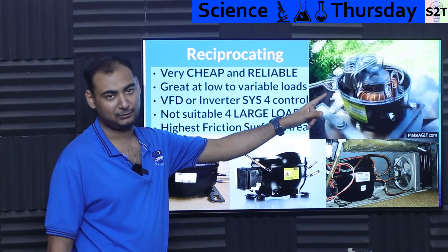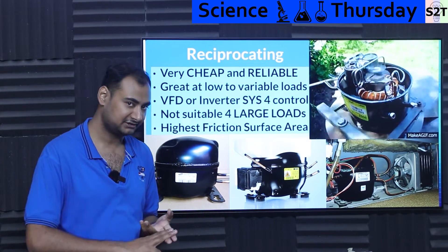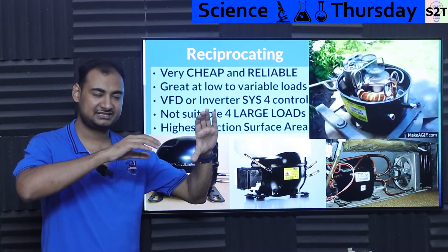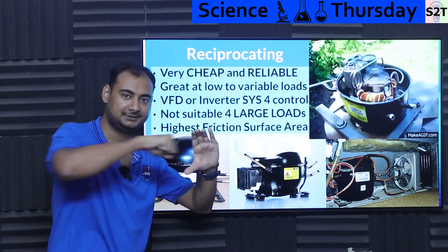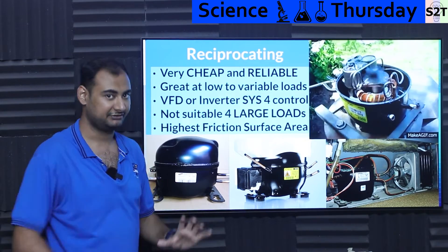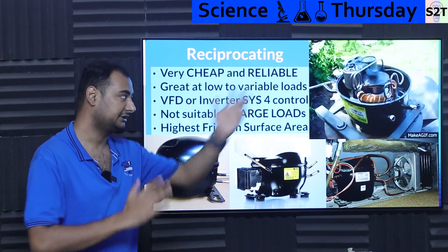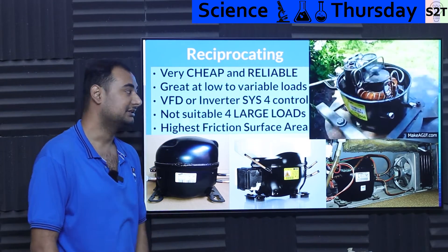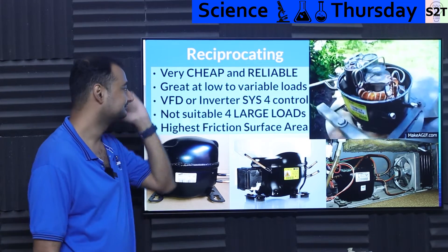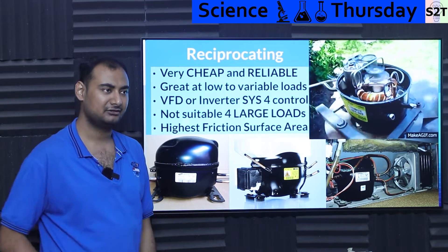The reciprocating compressor has too many friction points and is not designed for very long continuous duration. The friction in the compression chamber is significant — the piston bore means the entire cylinder wall is a friction surface. That's a significant amount of your energy. It does work — that's why you have a refrigerator — but if you try to run it for very long durations it doesn't work out well. Reciprocating: a good system, not great — a good starting point for low load.